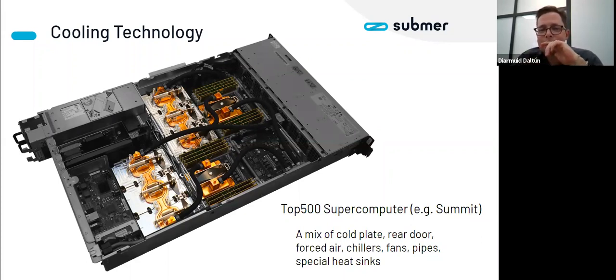Going back to the technologies involved, we have direct to the chip cooling, and we have the rear door heat exchanger, so the heat released at the back of the rack is captured by a rear door heat exchanger, which is also liquid cooled. So two different types of liquid cooling technologies.